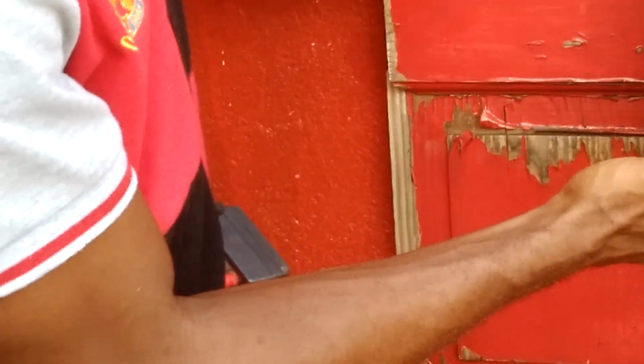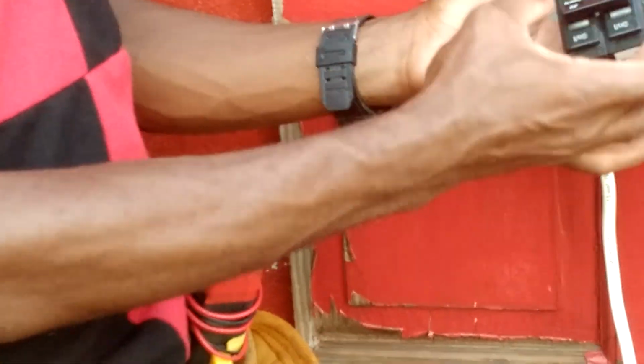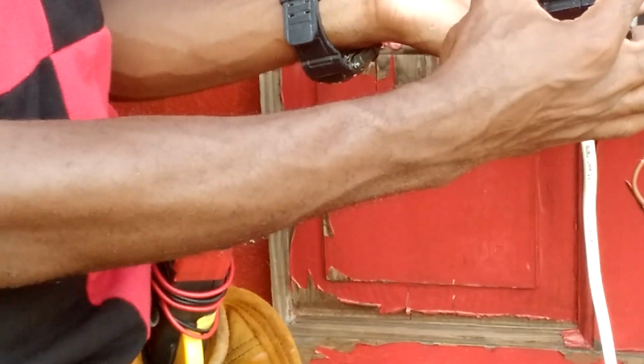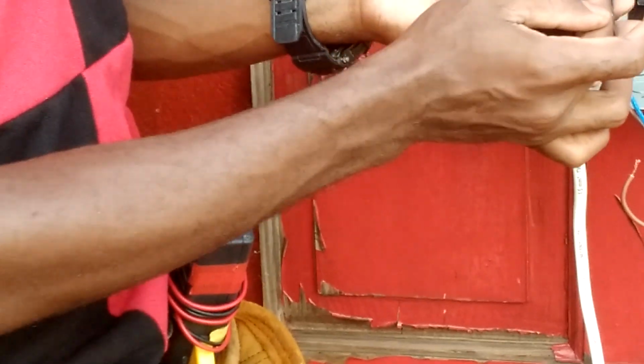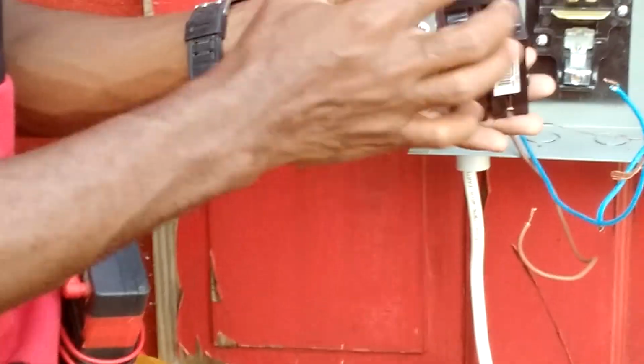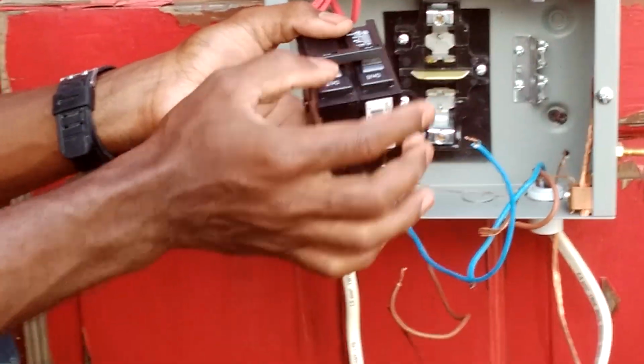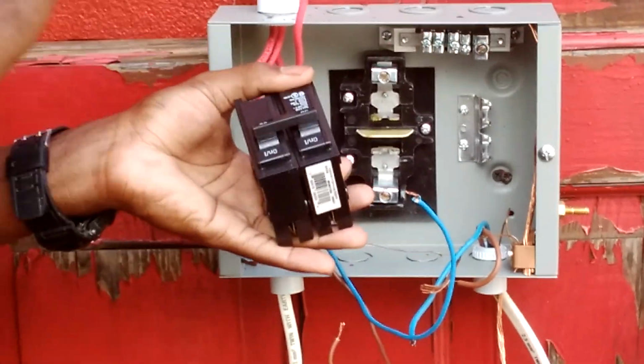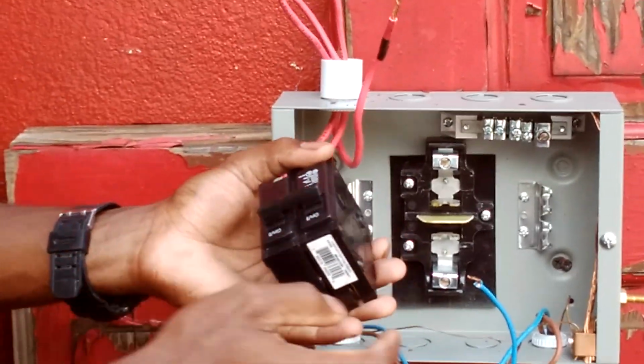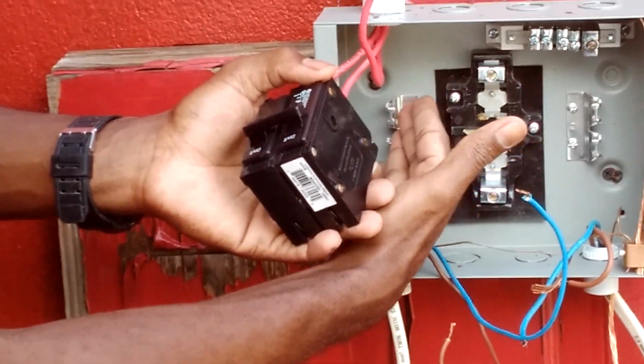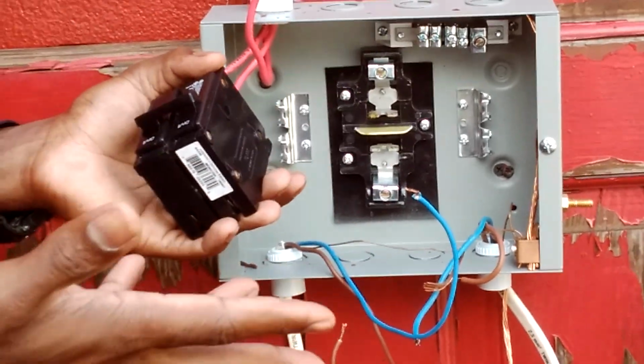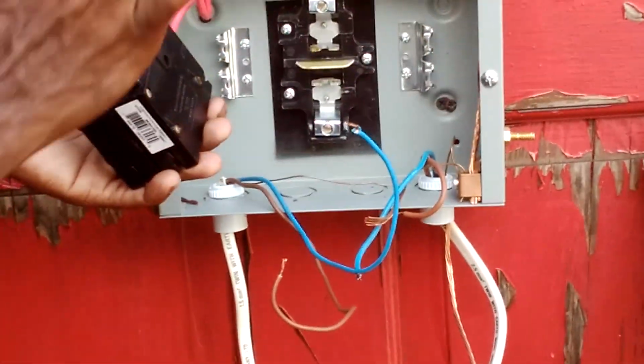So we're going to install this breaker now into the panel box. This 30 amp breaker is designed as a main circuit breaker — it's actually two breakers combined, with a connector hooking them together so they can be turned on and off at the same time. It takes up two spaces, so one half of our four-way panel box is already taken up, leaving only two spaces remaining.